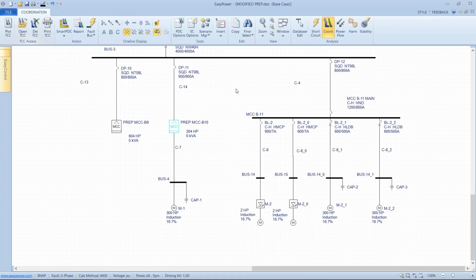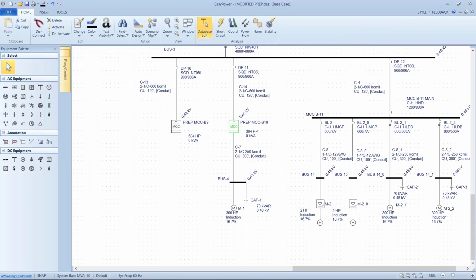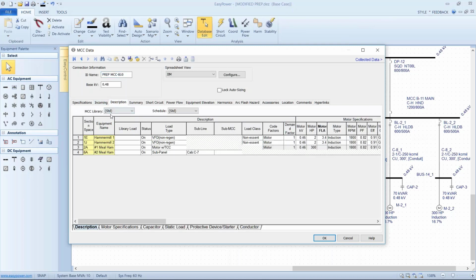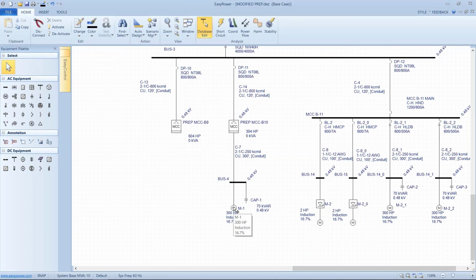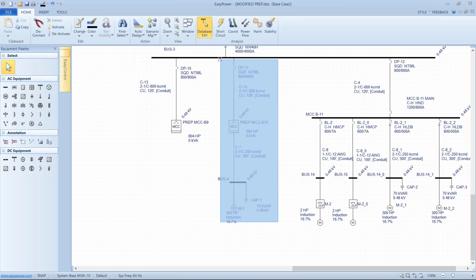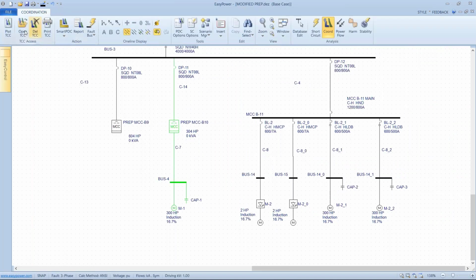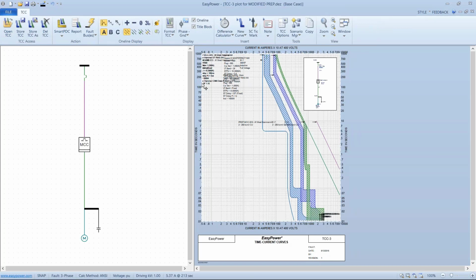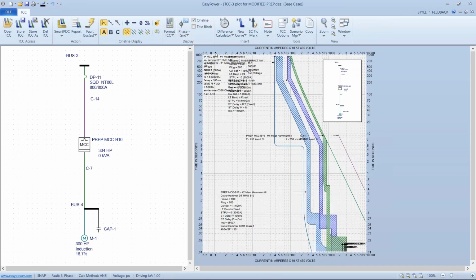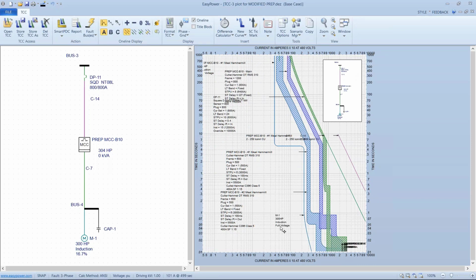And the way you do that, if we go into our motor control center, let's go ahead and not save anything. Back in database edit, my motor control center, if I look at the description, now instead of a motor with a TCC, which I can include for the other 300 horsepower motor, I've outboarded this through a cable, and now my load will be determined by this particular icon, and my feeder breaker can be coordinated with the main breaker in that case. So now if I select and go into coordination and plot, I can fault that bus downstream of that first breaker, and I can make an understanding or comparison.